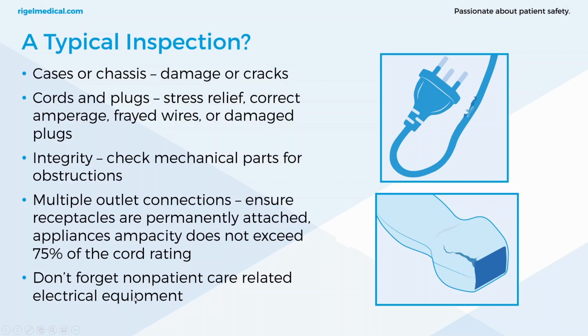Also, one thing to mention is don't forget non-patient care related electrical equipment. Now this is stated in NFPA 99 that it must also be inspected by the staff or other personnel, and that's not just equipment that's owned by the facility, but also any patient-owned appliances which may be used in that patient care facility and may come into contact with a patient. It's not in this current slide, but the patient care facility is mentioned in NFPA 99, what that area is. Maybe I might add that into any future presentations. That's something that I've just realised is not on these slides.